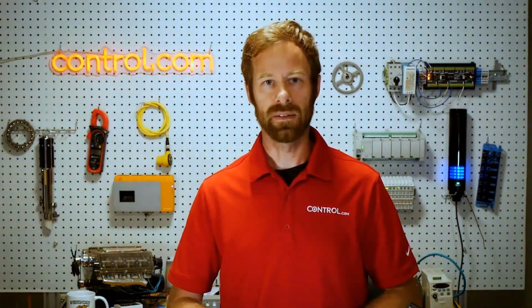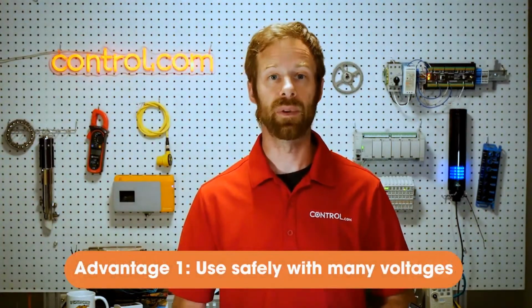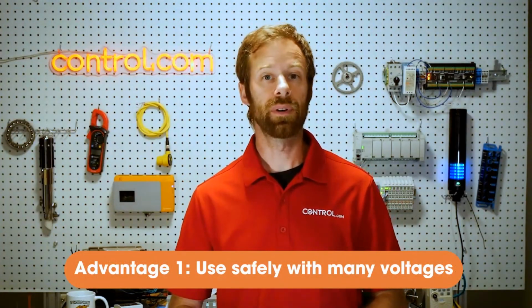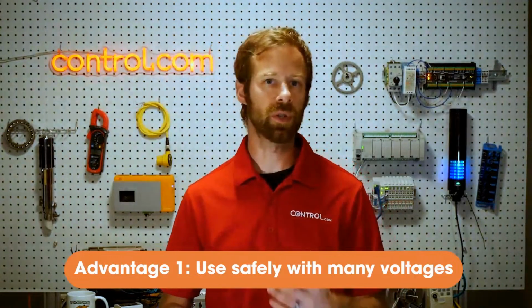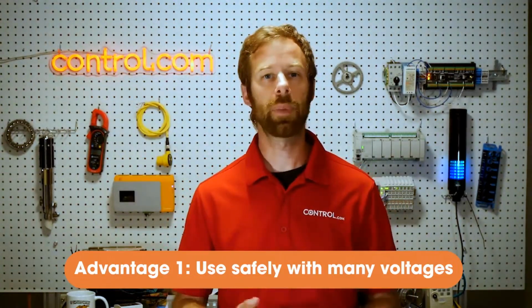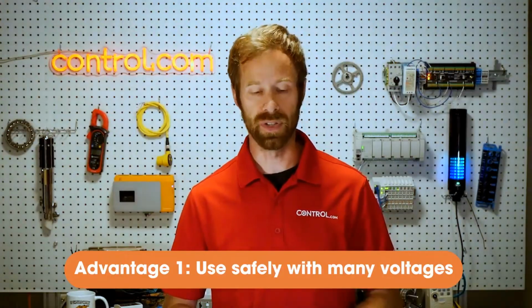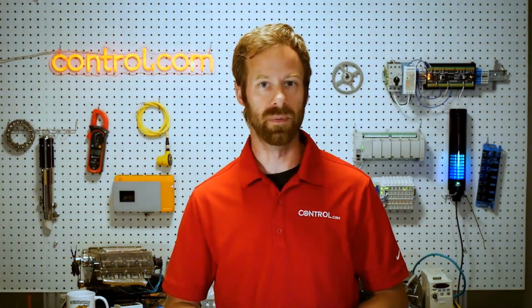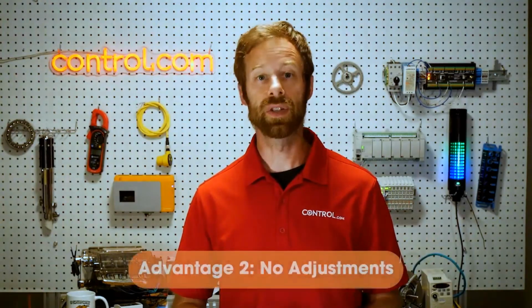So what's a huge advantage of these, or where are they used? Well, since there's no circuitry inside, first, we can use it safely with many different voltages. We don't have to worry about whether it's designed for 5 volts or 12 volts or 24 volts. They're compatible with most all control system voltages. Now, not all control system voltages, because there are some control systems that can operate at 230 volts or even higher, so we do have to look at those data sheets and make sure that we're not providing too much voltage, because of course we don't want to damage anything. Another great advantage is that there's no adjustments.